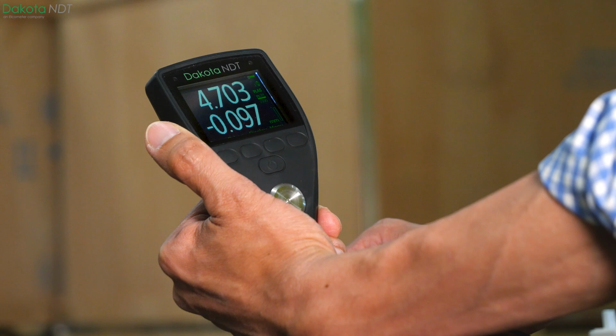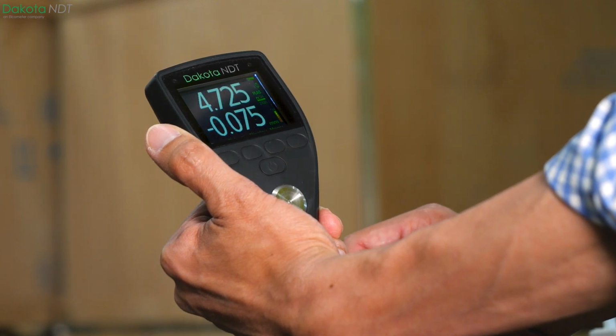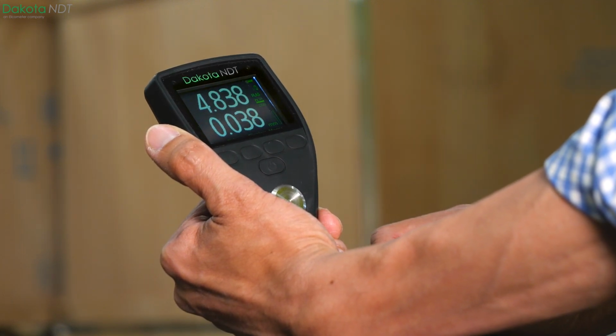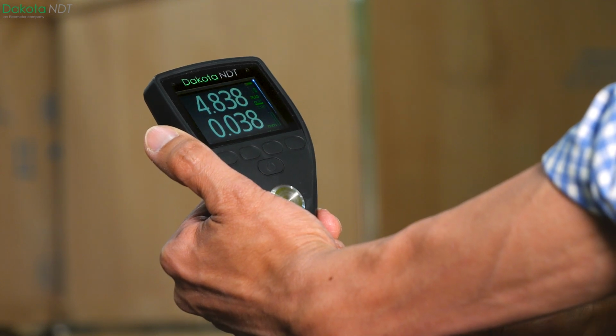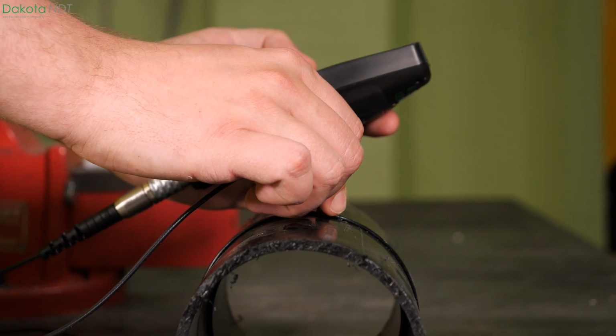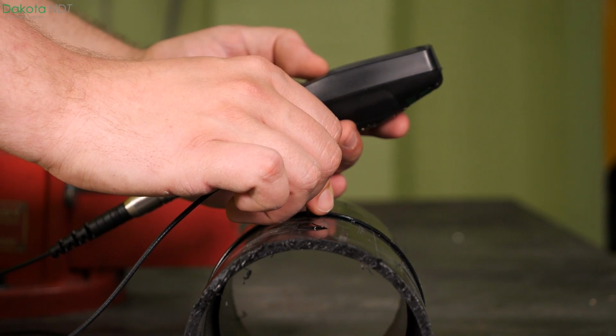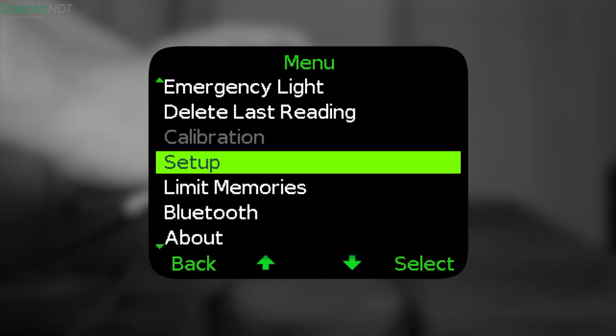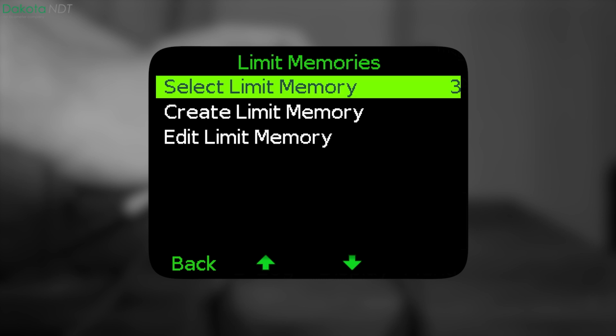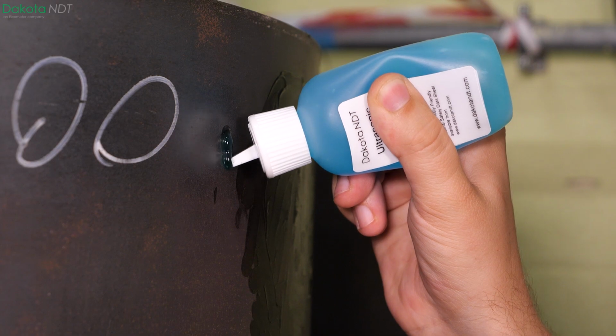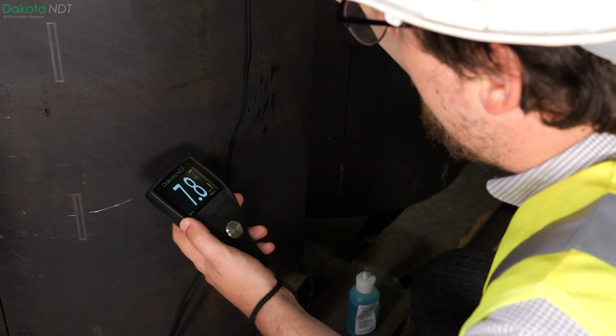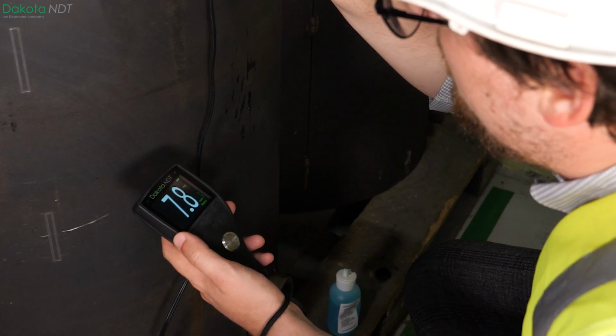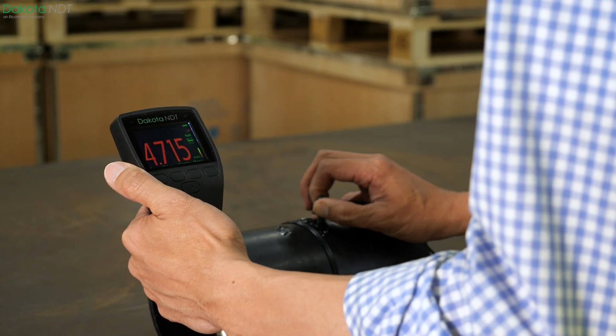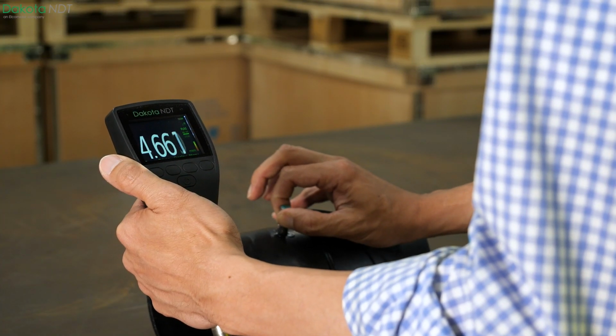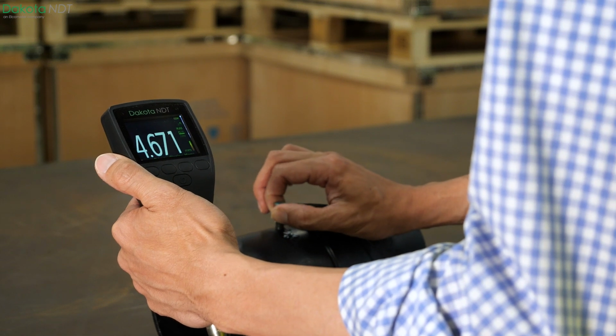Alternatively, Differential mode displays the last reading and how much it differs from the user-definable nominal value, also known as the target thickness, indicating where the material is thinner or thicker than expected. With limit memories, the DakotaNDT PCX8-DL allows you to set high and low limits, as well as previously mentioned nominal target thickness. Once defined, whenever a reading exceeds these limits, the gauge gives you an audio-visual warning, clearly highlighting any problem areas.